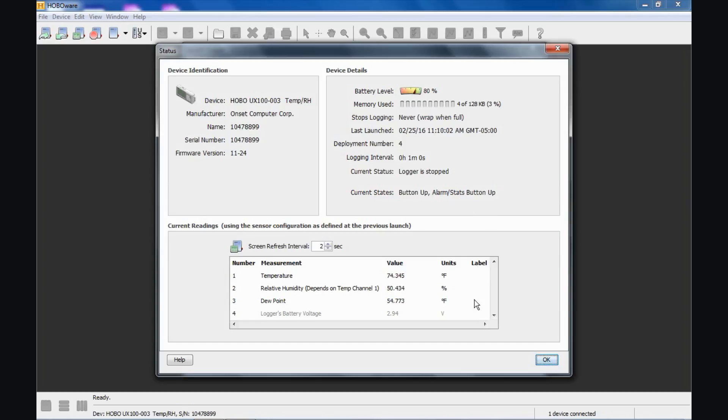Below that, we can actually see what the sensors are currently reading, the internal sensors of this data logger, as well as the calculated dew point, which HoboWare calculates for us. Keep in mind that when you are in this status screen, the logger is being kept awake and the sensor is being kept active, so it is using more battery than it normally would when it is logging. Again, this is just a quick status check.